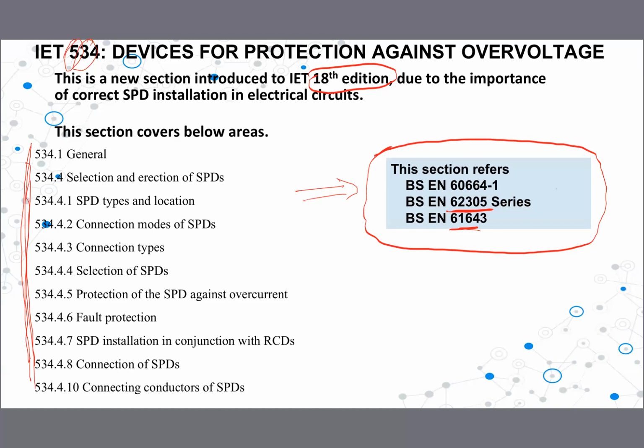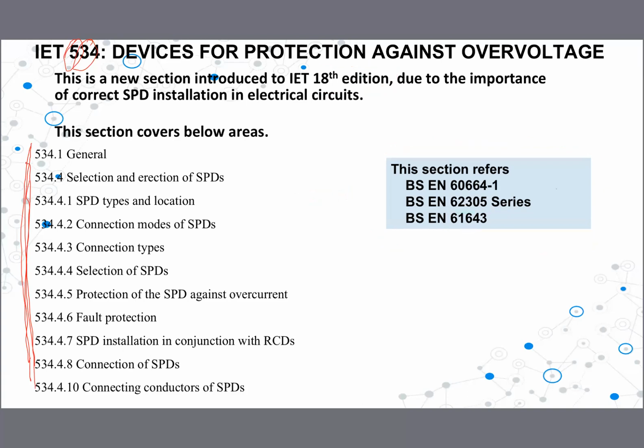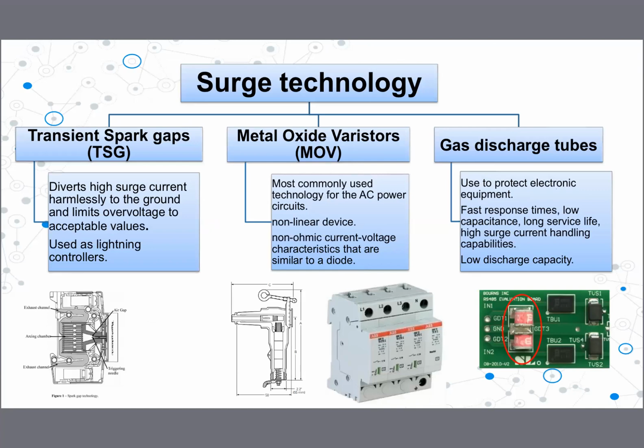Now, you need to understand, you need to get an idea. The surge protection design is clearly defined in the IET regulation, where it was not in the previous edition, the 17th edition, right? It's a new addition, one of the additions in the 18th edition, right? Then let's look at what the different technologies are that we use for surge protection devices.